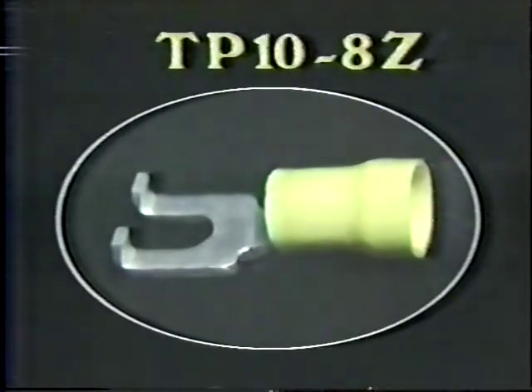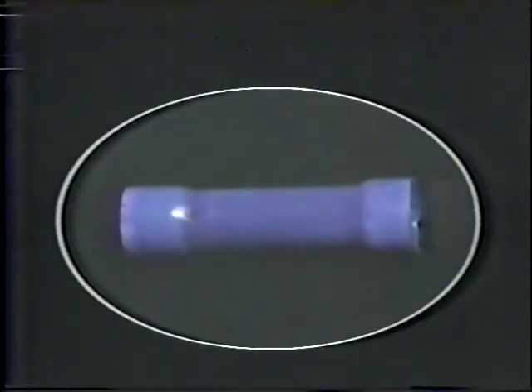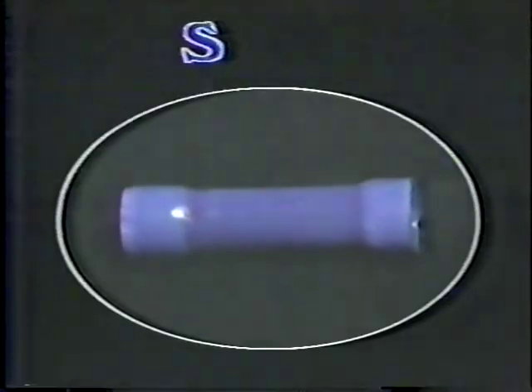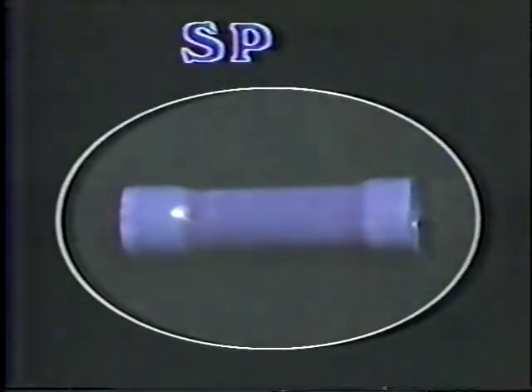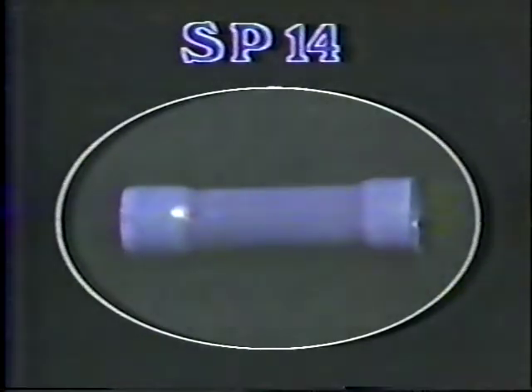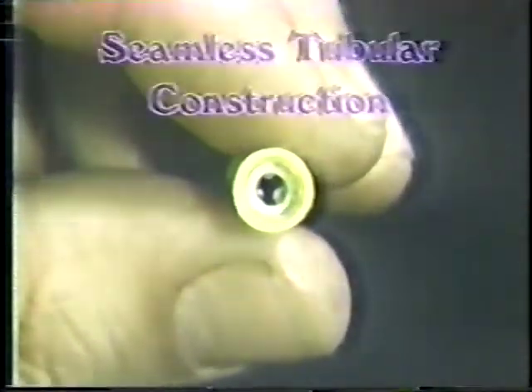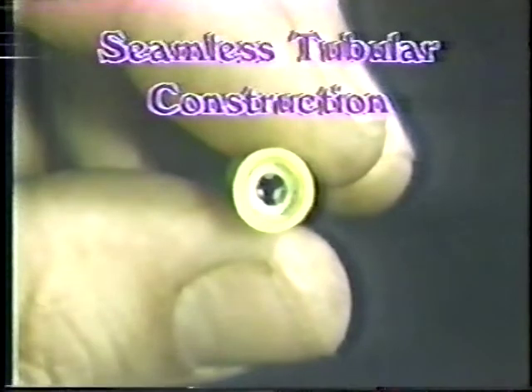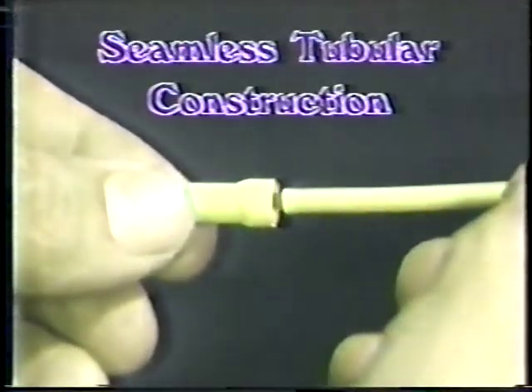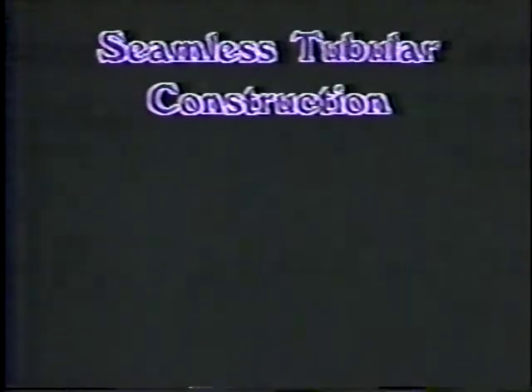A vinyl insulated splice would be designated like this: S for splice, P for polyvinyl chloride insulation, and the wire size that can be accommodated, in this example, a number 14. As with our nylon insulated splices, Burndy vinyl links feature a seamless tubular construction. This is particularly important with vinyl since the opaque material makes it difficult to see and position a seam for proper installation.